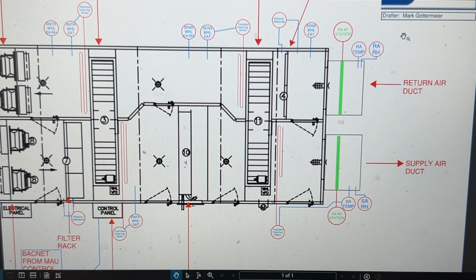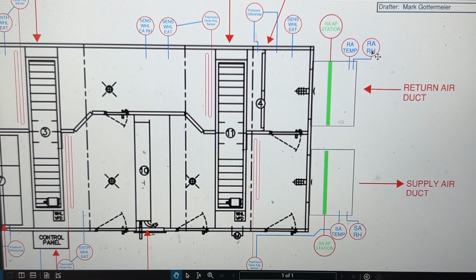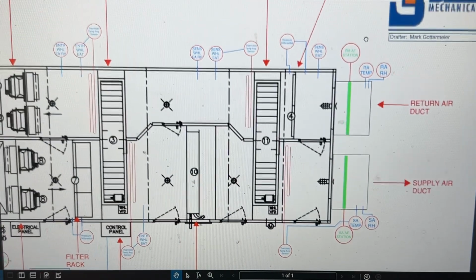Again, it's a heat pump system. So that return air, which gets pulled off of the exhaust, so we're adding air and we're also pulling it away based on the air changes needed. On the return air duct, we have a return air relative humidity sensor. We also have a return air temperature sensor, another flow station like we touched on earlier.